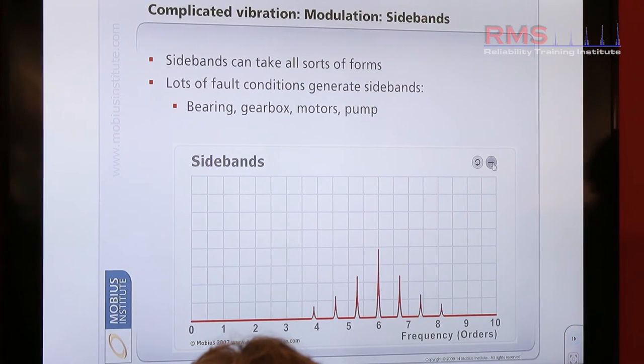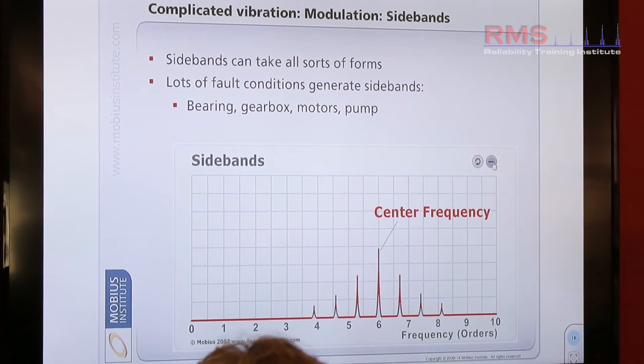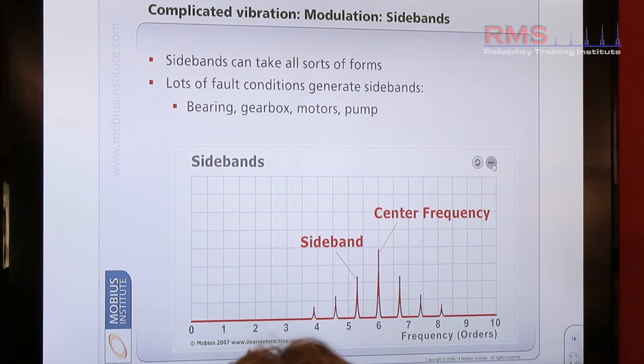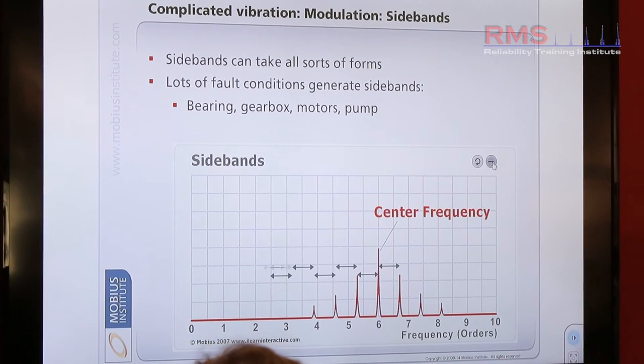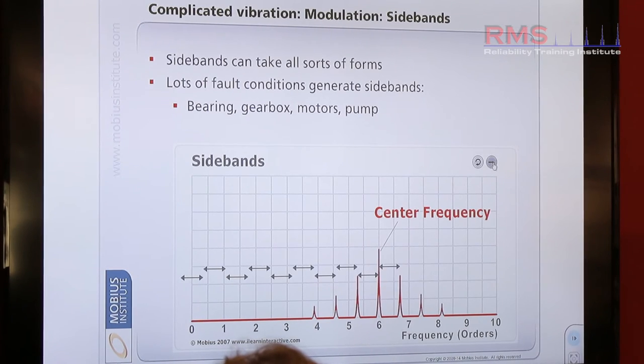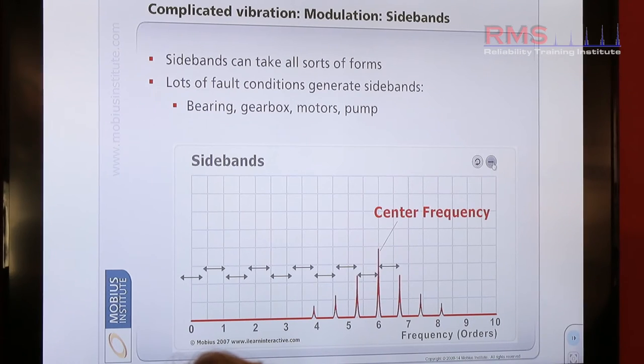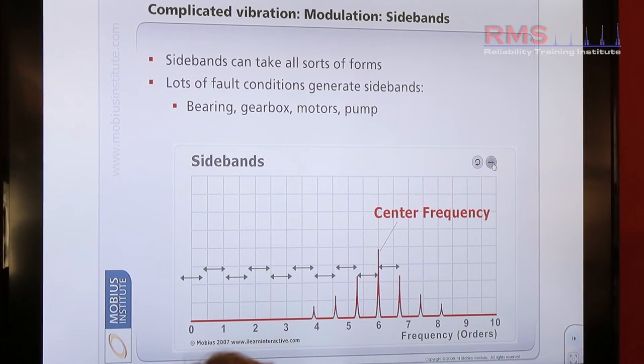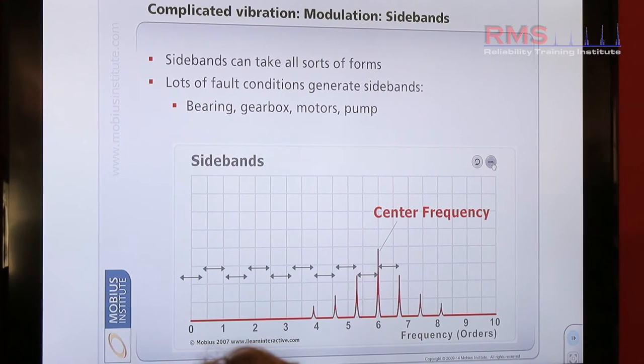So here we have several peaks equally spaced either side of the center frequency. They are spaced by a delta — a difference in frequency that's known — and they're equally spaced. And they're common on bearing problems, gear problems, looseness, and maybe electrical problems might be another one as well, where we see that distinct behavior.